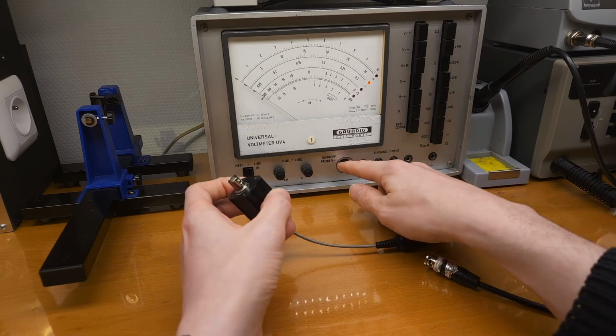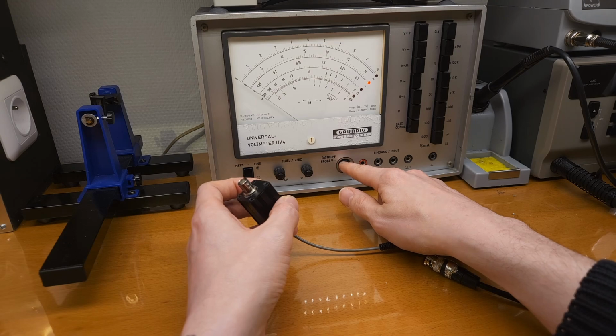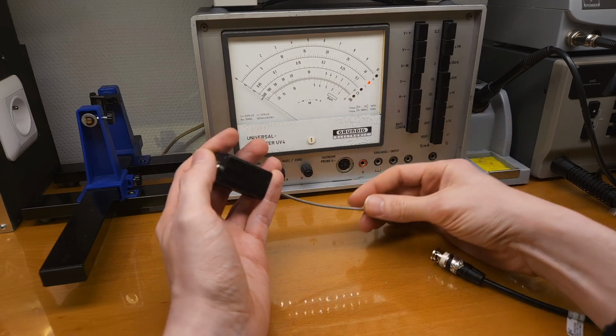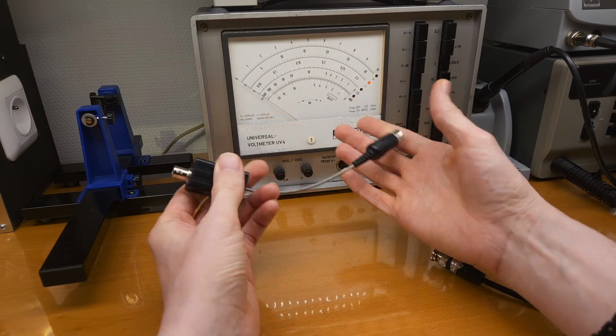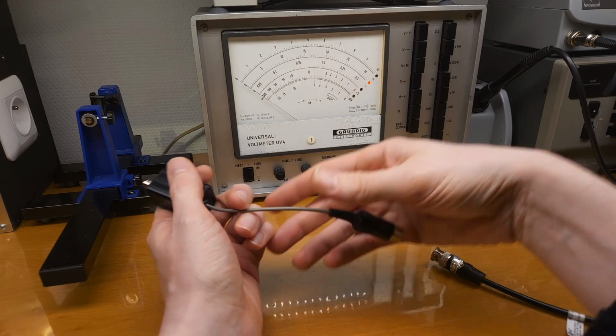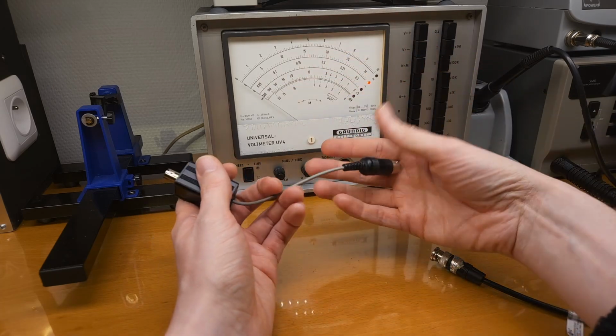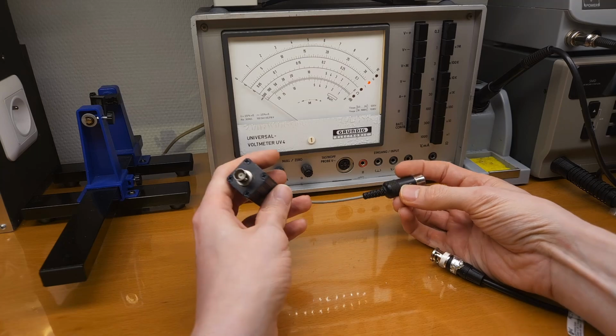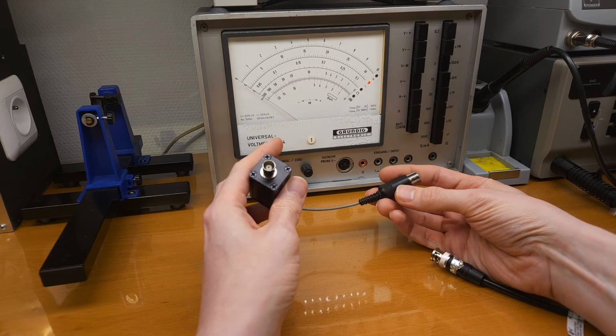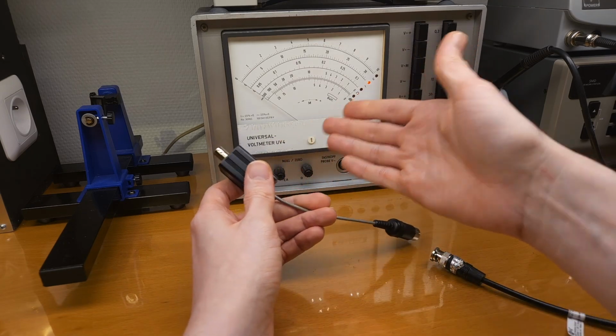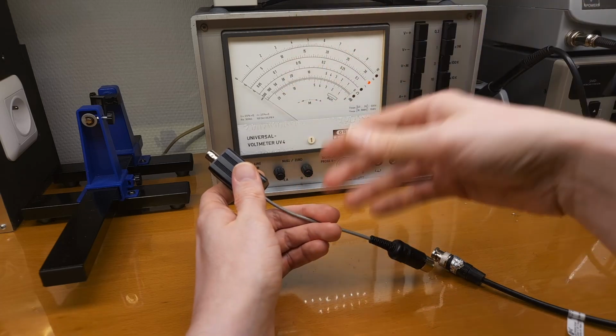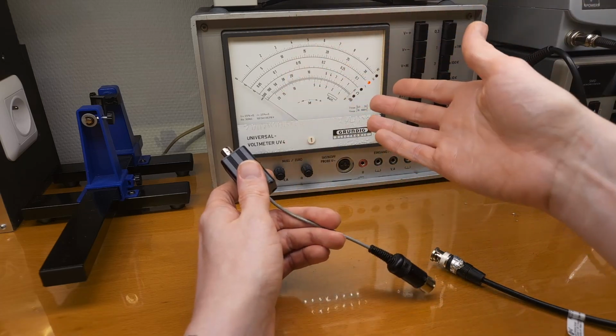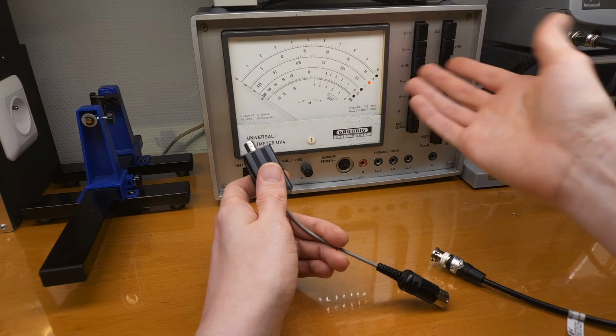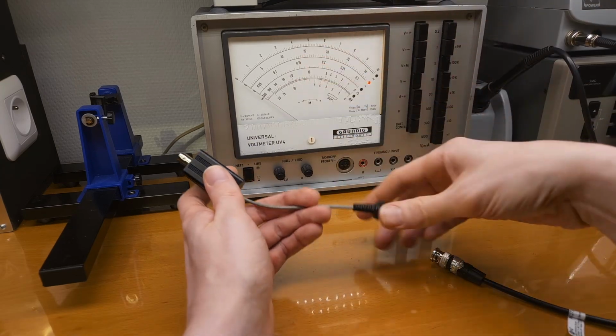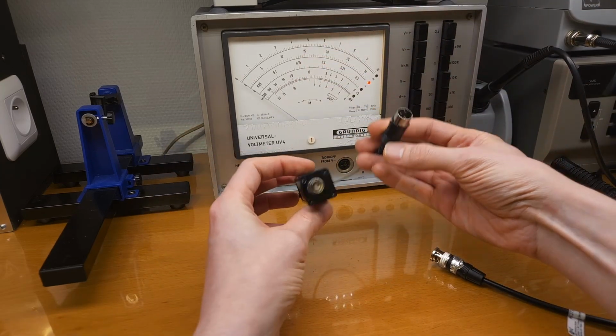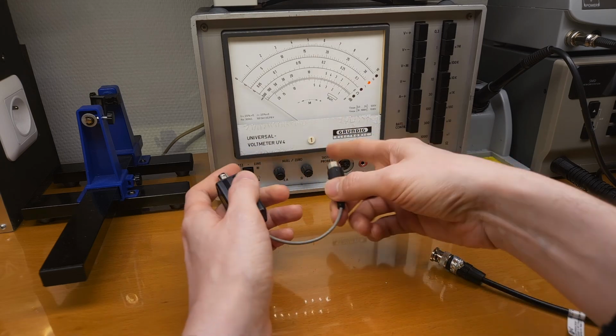Some people also build or add it inside the meter itself, on the inside of the socket, but I don't like to do that. This completely avoids changing the inner circuitry of the meter. I don't want to mess with or customize the meter itself. It's always, well, what happens if you pass this device on to someone else? Then they need to start reverse engineering everything that you changed in the circuit and all these things like that. I want to avoid it. And this way you can perfectly avoid changing anything in the circuitry.